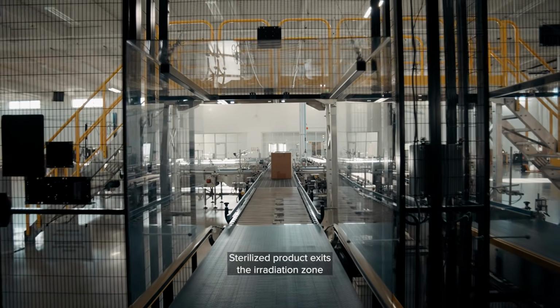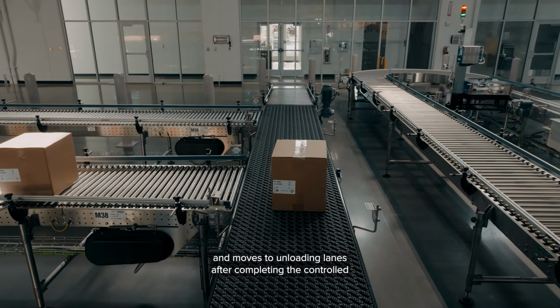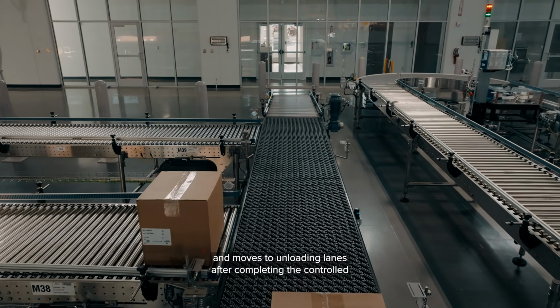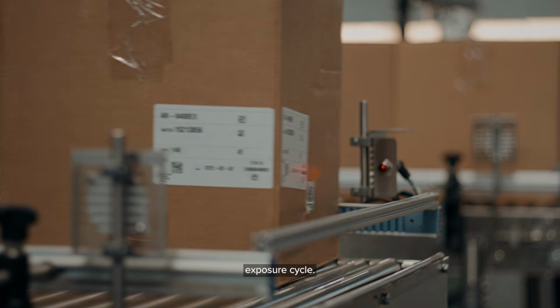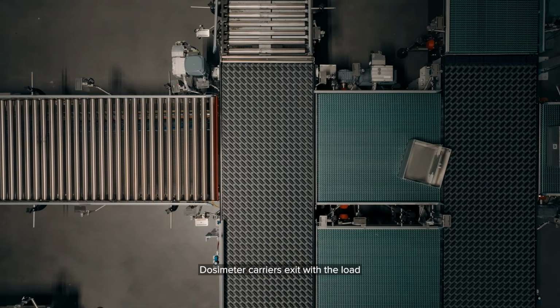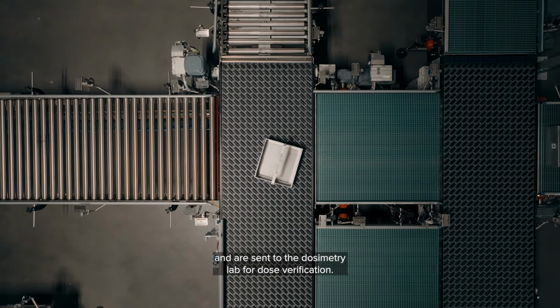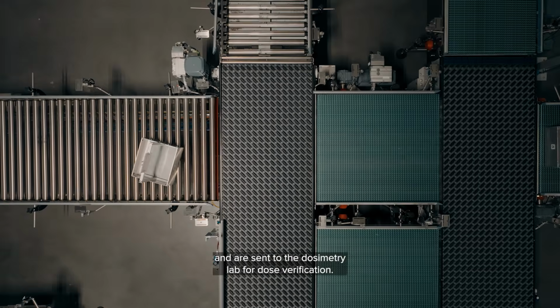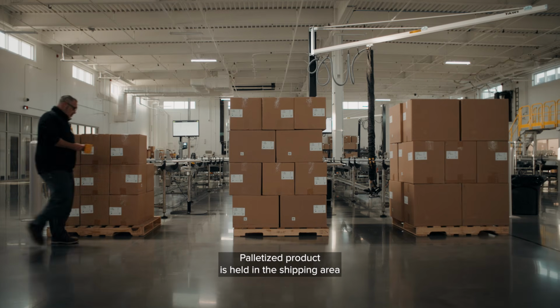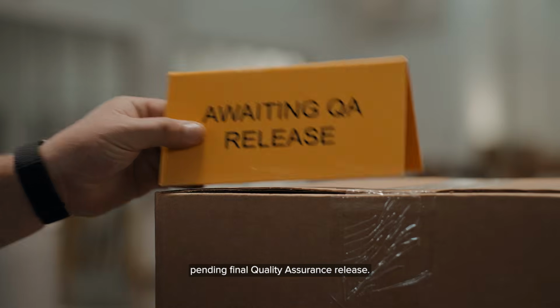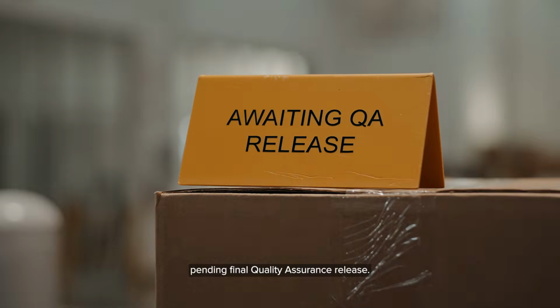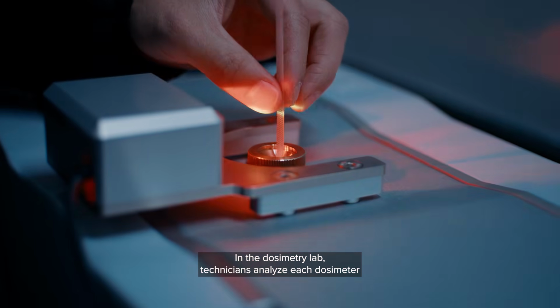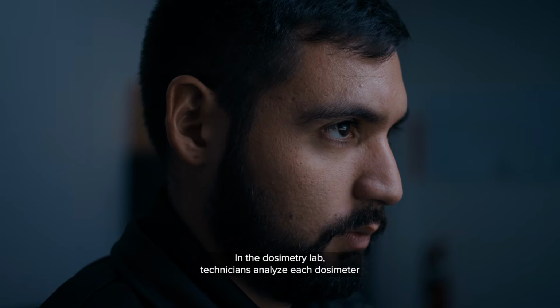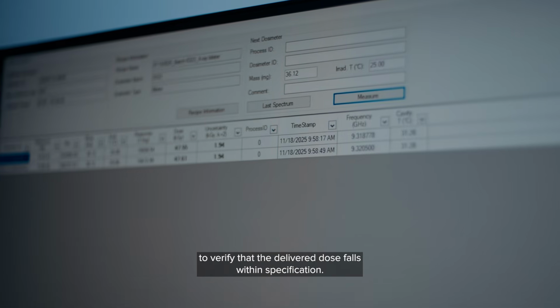Sterilized product exits the irradiation zone and moves to unloading lanes after completing the controlled exposure cycle. Dosimeter carriers exit with the load and are sent to the dosimetry lab for dose verification. Palletized product is held in the shipping area pending final quality assurance release. In the dosimetry lab, technicians analyze each dosimeter to verify that the delivered dose falls within specification.